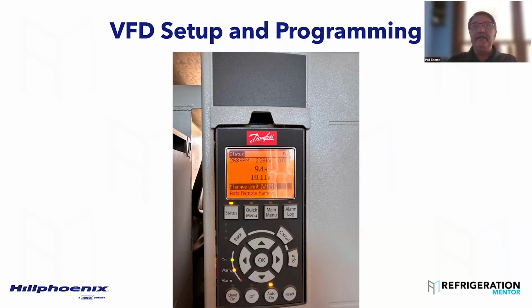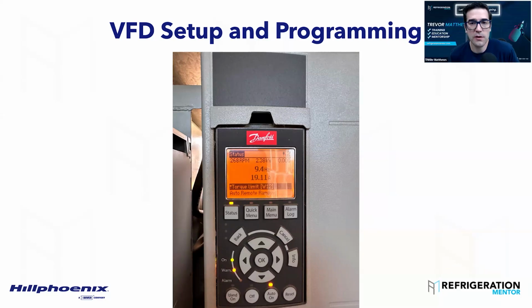25 hertz is fine, but be very careful. Once you go above 60 to 70 hertz, that compressor likes to let a lot of oil go out the discharge. Yeah, because of the carryover rate. You're spinning it faster, right? So the biggest thing is you've got to get into the Bitzer software or the Copeland software or the Dorin software, or whoever the compressor manufacturer is, and look at their limitations, and make sure that you're following their guidelines, right? Because I've seen contractors run it outside the guidelines, and then the compressor fails, right? Or run into a lot of issues with those compressors.